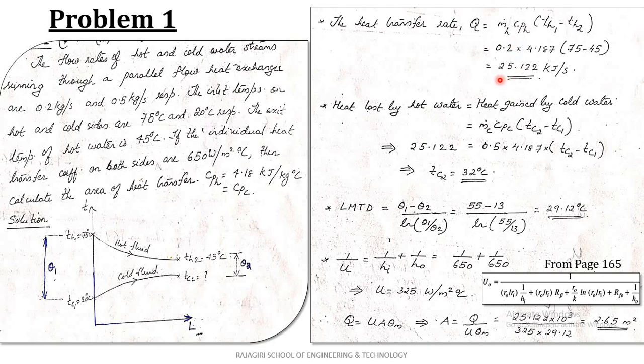The heat transfer rate is Mh·Cph·(Th1 − Th2): the mass flow rate of hot fluid is 0.2 kg/s, Cp is 4.18 kJ/kg·K, giving a heat transfer rate of 25.122 kJ/s (kilowatts). Equating this with Mc·Cpc·(Tc2 − Tc1), you can calculate Tc2, which is 32°C.